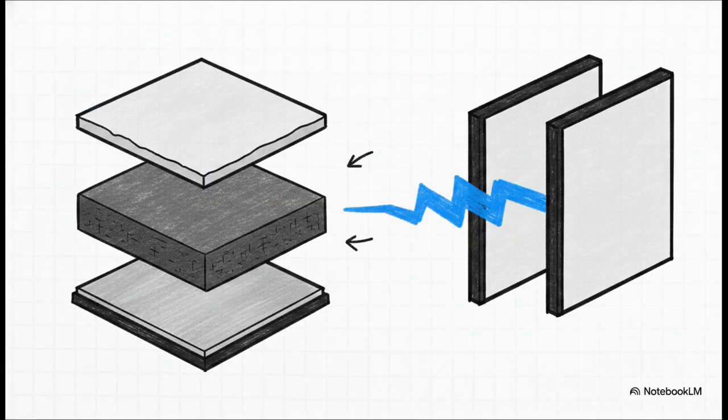Step 3 brings us to the panels themselves, and honestly, these are serious engineering marvels. A typical panel features a calcium sulfate or concrete-filled steel core that rests on a galvanized steel base. They've also got this cushioning layer and, absolutely crucially, an ABS trim around the edges. Now, this trim doesn't just stop physical chipping from happening, it ensures a totally consistent electrostatic discharge path across every single joint in this massive room.